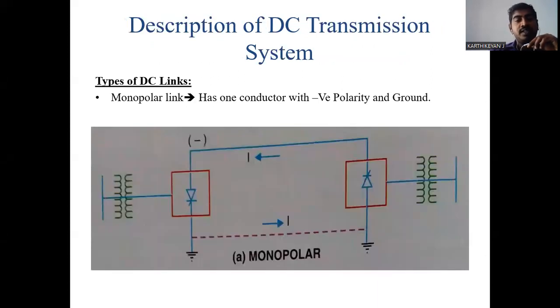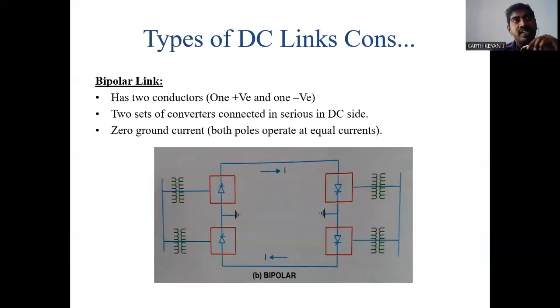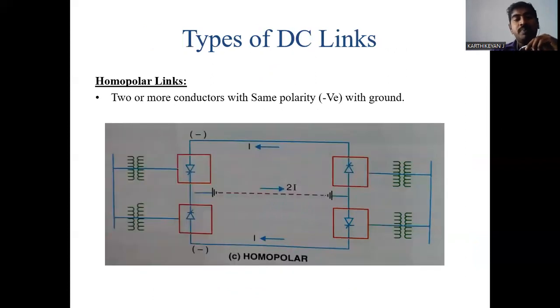The types of DC links are: monopolar link, bipolar link, and homopolar link. In a monopolar link, one conductor (the negative conductor) is grounded. In a bipolar link, there are two conductors — positive and negative — with two sets of converters connected in series on the DC side, with the negative side grounded. In a homopolar link, two or more conductors share the same polarity (negative), with the return path through ground.